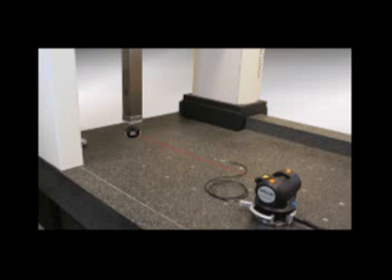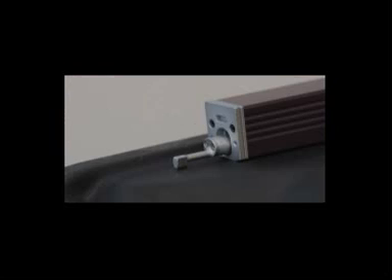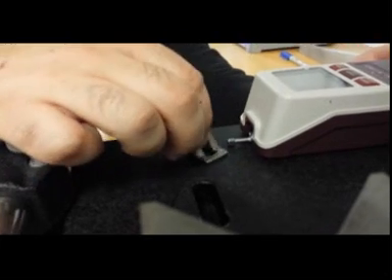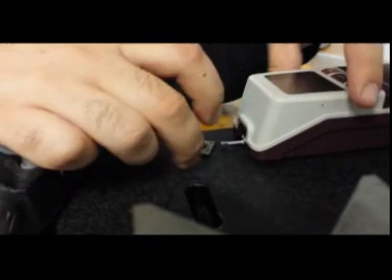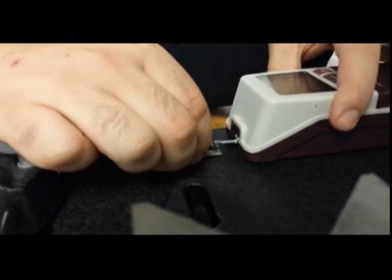We currently have access to a profilometer, a video inspection machine, and coordinate measuring machine or CMM available via the metrology lab located in building 41. The profilometer is a great way to find the average surface roughness of a sample. The probe sweeps across the face of the part and calculates the mean roughness. This method is useful when you would like to know if a part is in spec or not. However, it does not provide a point-by-point representation of the entire surface area. In addition, the probe is limited by its reach and clearance, which has caused us to modify the sample part.